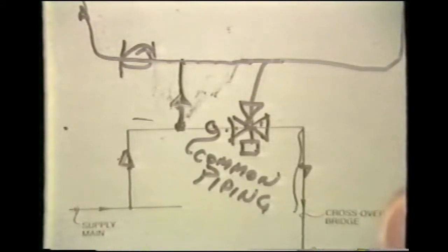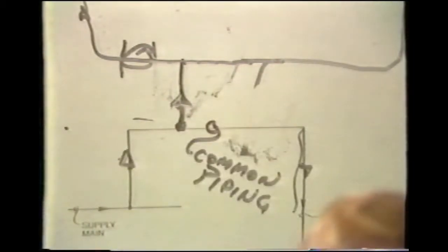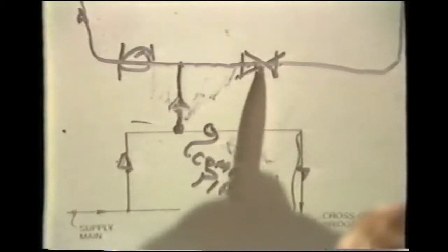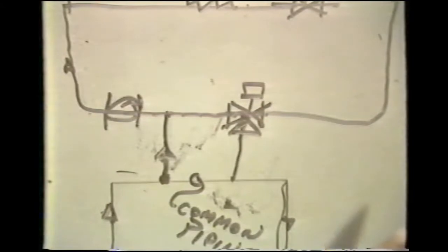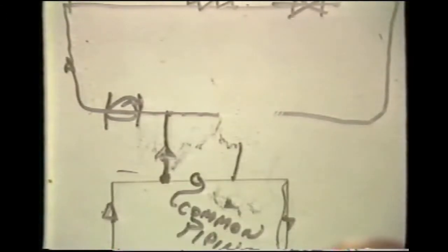The other potential thing that was done was to provide a diverting valve in the secondary circuit, a diverting three-way valve in the secondary circuit. And that diverting three-way valve eliminated the problem inherent to providing pressure to the pump suction in the secondary circuit. But basically, the true solution was to use the mix valve in the crossover bridge.